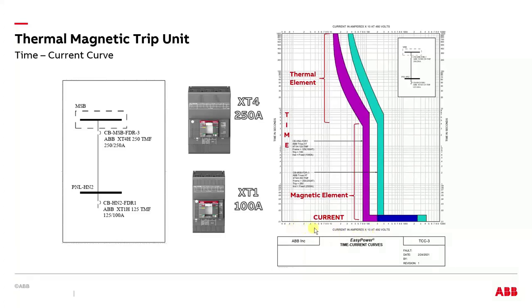You read it by, okay, I have a fault current of, let's say, where do we go here? That's amps, but I think this is times 10. So let's say that's a 250, 100. Okay, so here is 100 amps. So let's say I have 200 amps of a fault or overload, and the breaker will start the time, does nothing, and then it gets into this area. And this is the area where the breaker will trip, and it'll trip anywhere in this region. This is sort of an uncertainty region, an unknown band. So it could trip at the bottom, it could trip at the top.